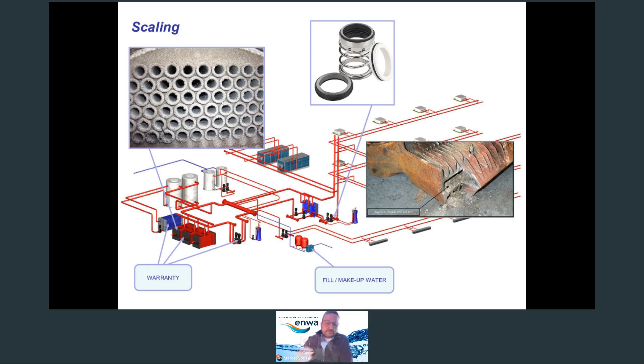The indirect cause of scaling is large particle generation, which again begins to clog up surfaces and heat transfer components such as plate heat exchangers. And there you see on the screen a picture, for example, of a cast iron boiler section where the insulation effect causes hot spots and failures, eventually leading to leaks and excessive top up also. So it's important to have that strategy also, which will advise on what the initial fill water should be.